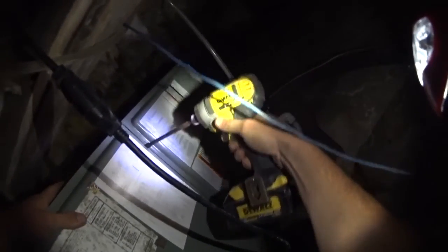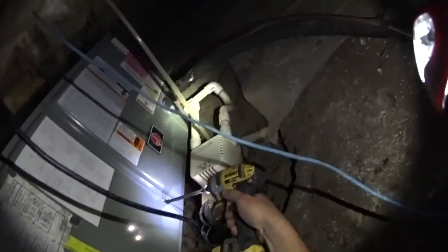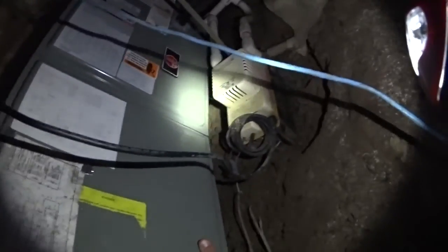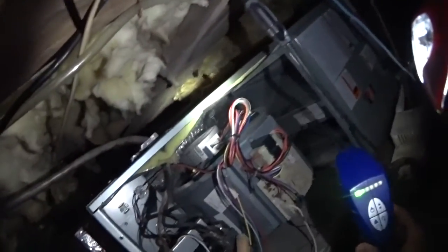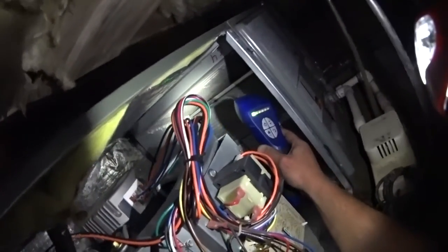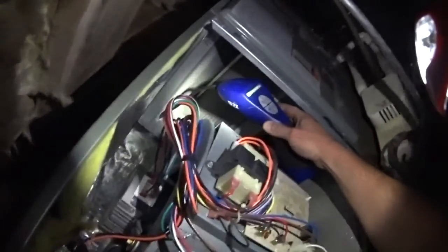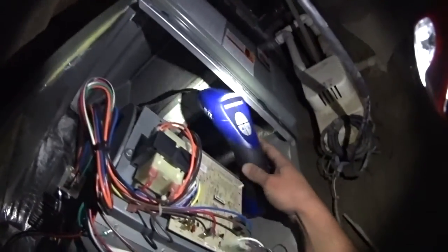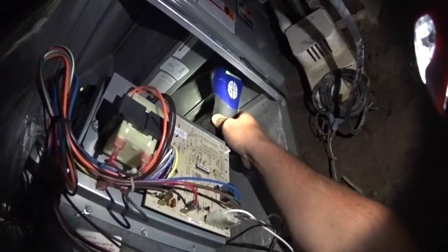A secondary condition that I had discovered actually as I was crawling out of this crawl space once I was finished was that someone had overloaded a crawl space electrical circuit. They had installed a dehumidifier, a condensate pump for that dehumidifier, and this condensate pump all on the same outlet. They had a big old splitter on it, and this pump was actually not working at all at the time, but obviously that's an electrical situation, something that an electrician's going to handle much better than I would. So I informed the customer of that and made sure that they knew that they would need to address that particular instance. At the time, I simply disconnected to prove that the pump was still good and it was not a pump failure issue.